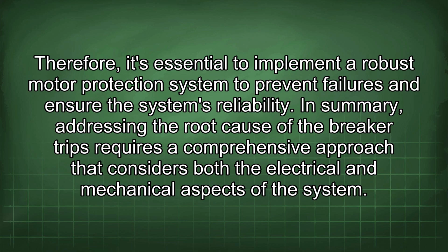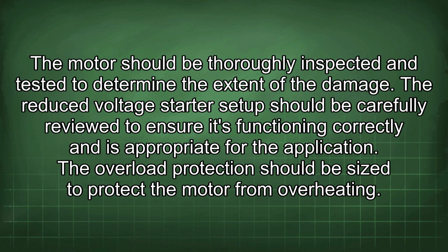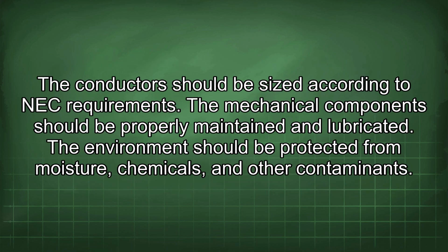In summary, addressing the root cause of the breaker trips requires a comprehensive approach that considers both the electrical and mechanical aspects of the system. The motor should be thoroughly inspected and tested to determine the extent of the damage. The reduced voltage starter setup should be carefully reviewed to ensure it's functioning correctly and is appropriate for the application. The overload protection should be sized to protect the motor from overheating. The conductors should be sized according to NEC requirements.